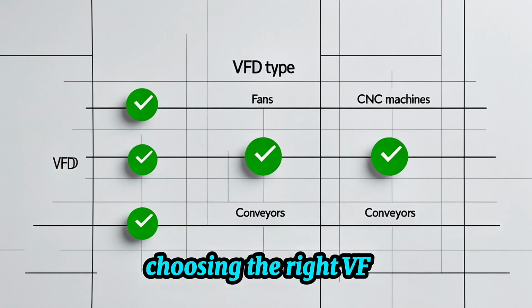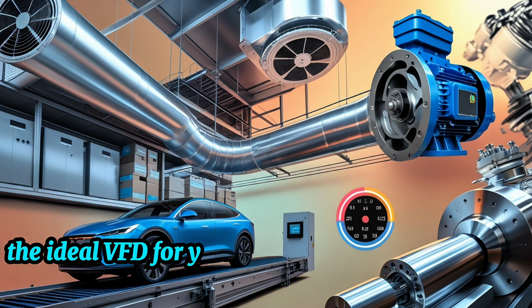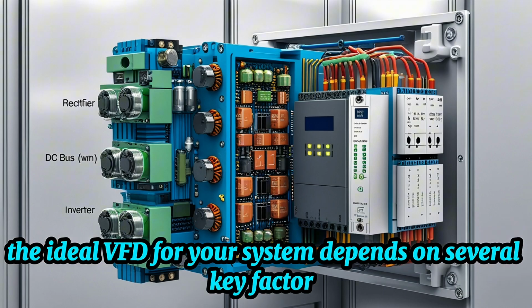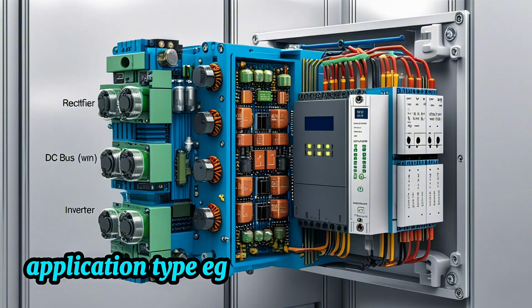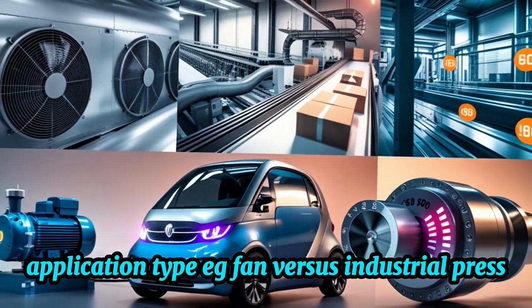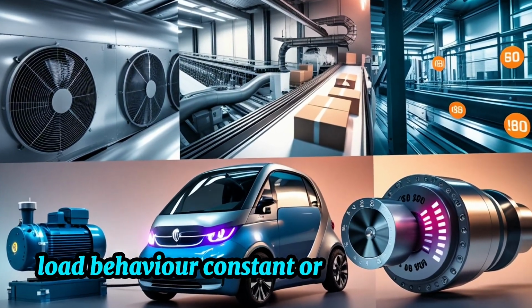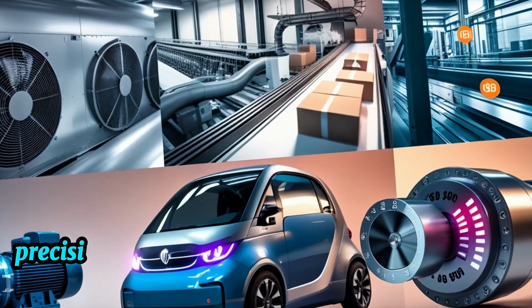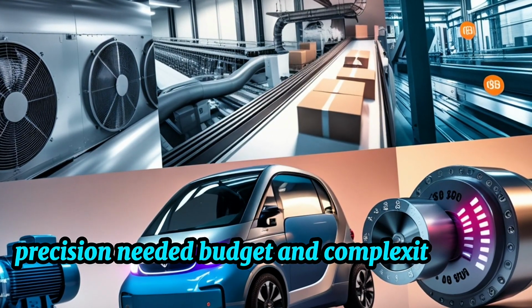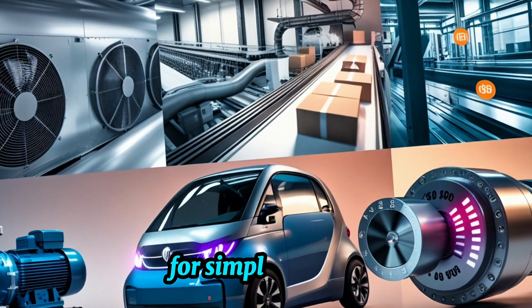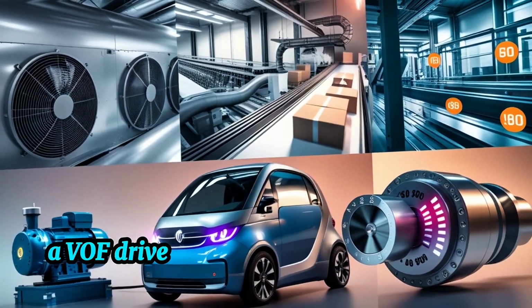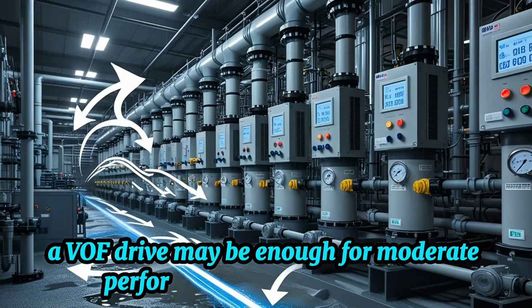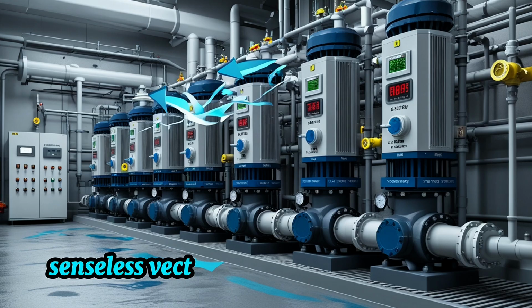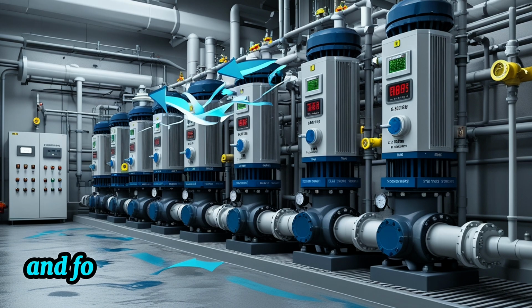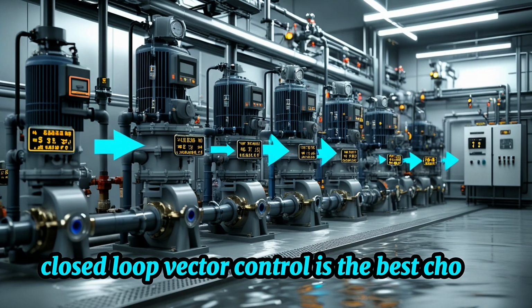Choosing the right VFD. The ideal VFD for your system depends on several key factors. Application type, e.g., fan versus industrial press. Load behavior, constant or variable. Control precision needed. Budget and complexity you're willing to manage. For simple systems, a V/F drive may be enough. For moderate performance without feedback, sensorless vector control is a strong option. And for high-end precision and torque control, closed-loop vector control is the best choice.